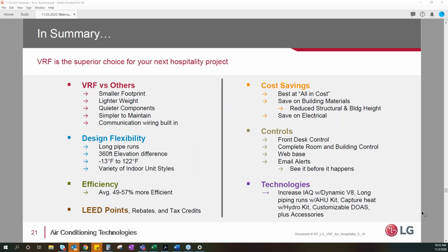And here they're just talking about some different efficiencies. Maintenance, let's talk quickly about maintenance. One of the big advantages VRF has is it's almost, I'm not going to say maintenance free, but it's basically just clean the coils and clean the filters. And that's pretty much the maintenance schedule for a VRF. There's no water or chemicals that need to be done. So that is one really big advantage that it has.